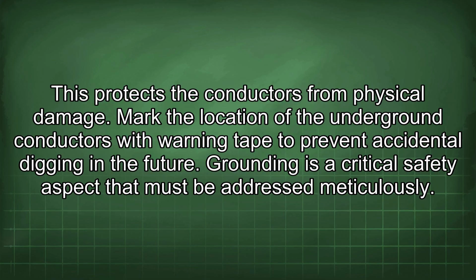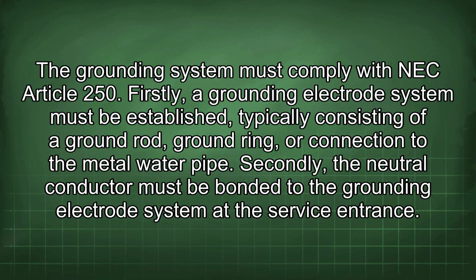Grounding is a critical safety aspect that must be addressed meticulously. The grounding system must comply with NEC Article 250. Firstly, a grounding electrode system must be established, typically consisting of a ground rod, ground ring, or connection to the metal water pipe. Secondly, the neutral conductor must be bonded to the grounding electrode system at the service entrance.